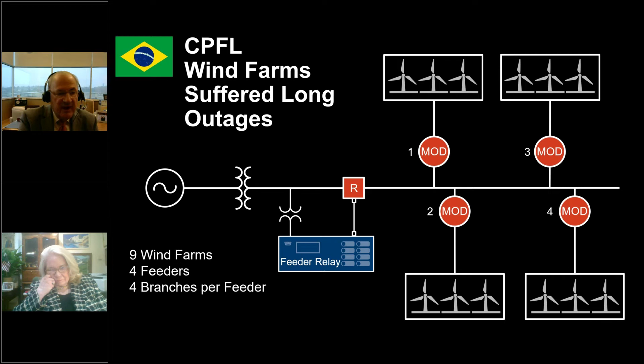Maintenance folks would have to go out and patrol to see where the fault was, operate one of the motor-operated disconnects to isolate the faulted part, then come back and turn the wind farm back on. They got tired of doing that—it was expensive losing the very clean green energy the wind farm was built to produce. Across 9 farms, this was a major challenge.